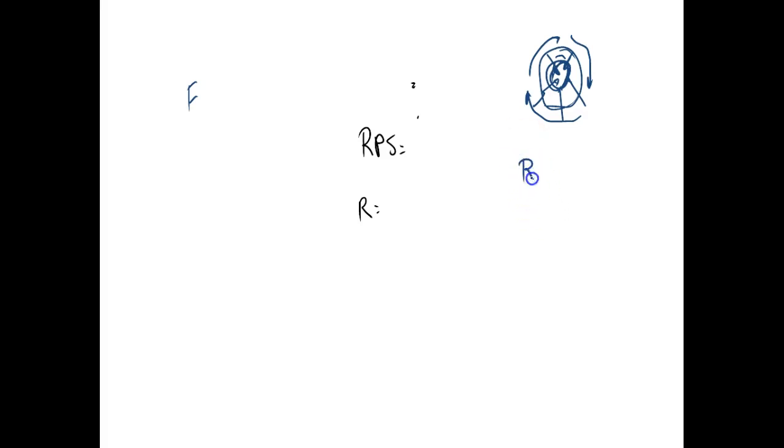speed. So the speed of an AC motor is equal to 120 times the frequency divided by the number of magnetic poles, and then minus the slip. So that's the actual speed of an induction motor. So if you know the percent of slip that the motor had, then you can literally count the speed. Okay. So we got 2 things we need to do. So it looks like I can't change 120, because by the way, this is the frequency. Alabama Power runs at 60 cycles.